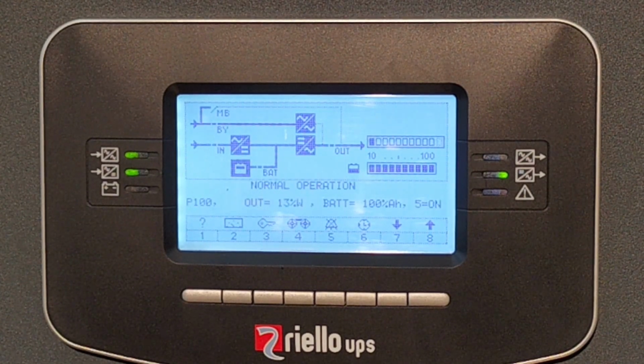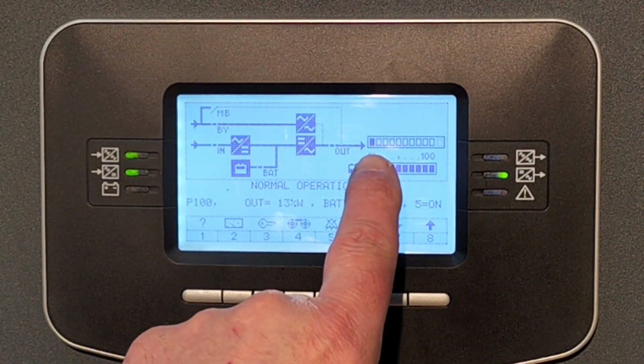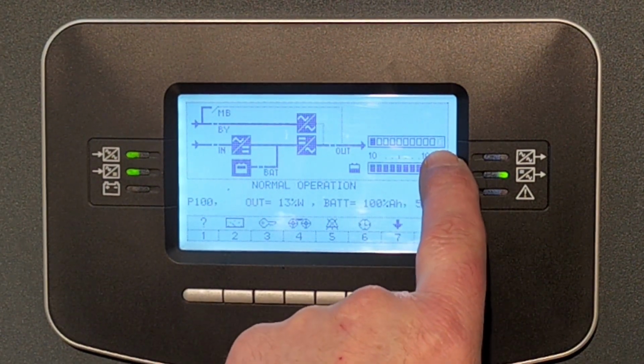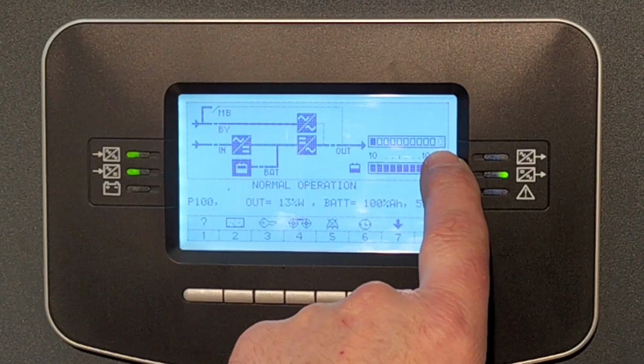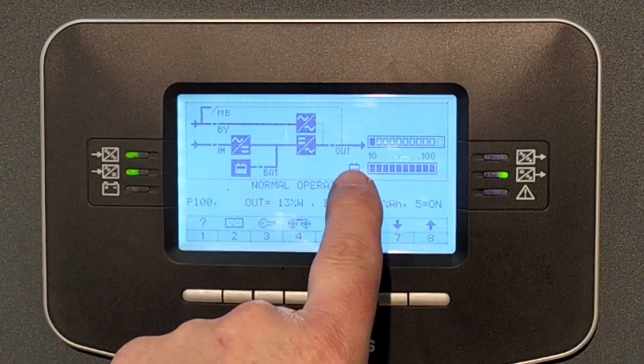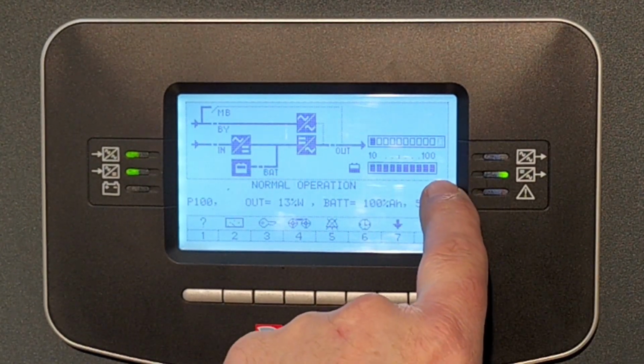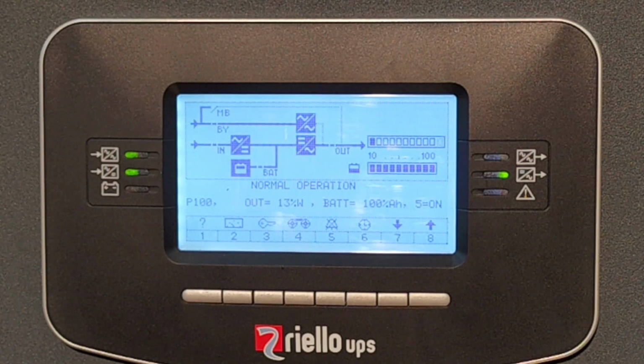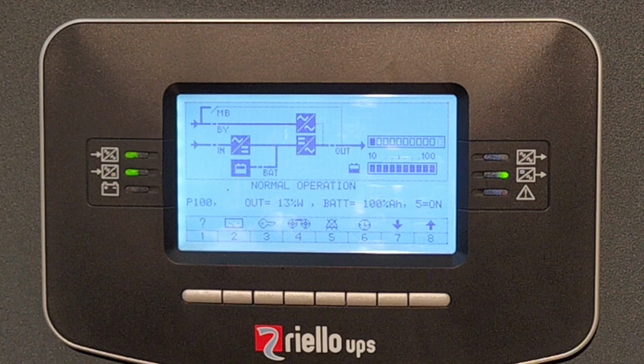The UPS is now in a normal operating mode. The top bar indicates load capacity, currently at about 10%. The bottom bar indicates battery capacity. These batteries are fully charged. The LEDs are indicating that the static switch has power, the rectifier has power, and on the right-hand side the inverter is functional. Green lights, all good.